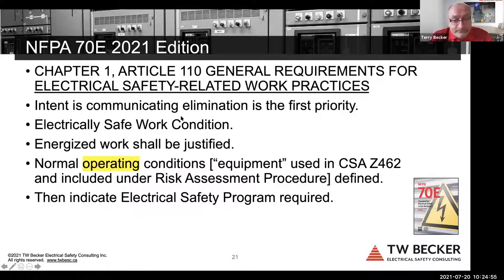Now, again, the intent is that we want this whole thing to be about eliminating exposure, and it's the first hierarchy of risk control method of the 6 hierarchies that are listed in 70E and Z462, but then 70E and Z462 allow energized work. I get comments, well, we can't work energized, it's against the law. And I said, well, no, it's not against the law. 70E and Z462 allow it, but there's a methodical process that you have to follow. And I frame it under what I call an energized electrical job workflow, right? So I've got this energized electrical job workflow. And again, when I'm on Zoom with my background, you can't see it 100%, but this workflow is how I frame this when I talk about it with users, right?